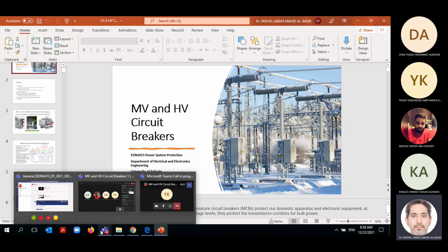Yes. Okay. I am telling you this is like open air substations, and the one that opens here is like a switch, or a disconnector. But as you can see, it was a load condition. This was not during a short circuit. But see the arc, the plasma. It can extend until it's extinguished. So when you open a breaker, from the moment of physical opening, it doesn't mean it is electrically disconnected, because the current will flow through the arc. So until all the arc is extinguished, we do not say the current is broken or the fault is cleared. Okay.